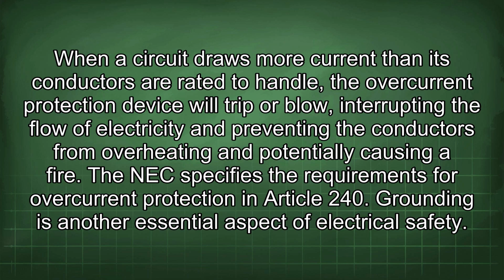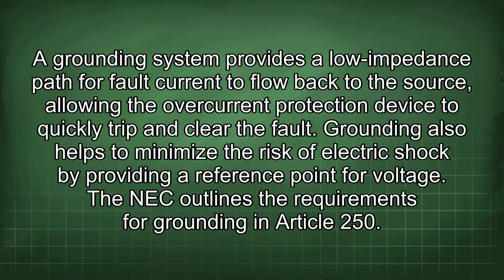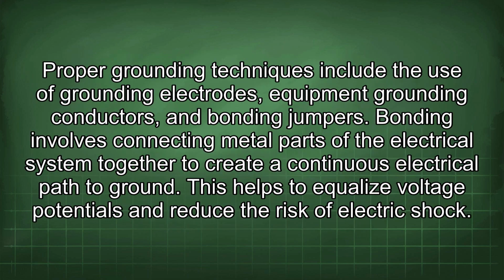Grounding is another essential aspect of electrical safety. A grounding system provides a low impedance path for fault current to flow back to the source, allowing the overcurrent protection device to quickly trip and clear the fault. Grounding also helps to minimize the risk of electric shock by providing a reference point for voltage. The NEC outlines the requirements for grounding in Article 250. Proper grounding techniques include the use of grounding electrodes, equipment grounding conductors, and bonding jumpers. Bonding involves connecting metal parts of the electrical system together to create a continuous electrical path to ground.